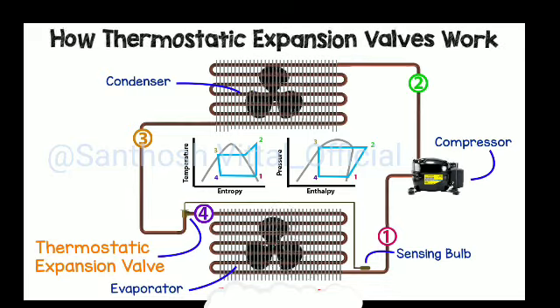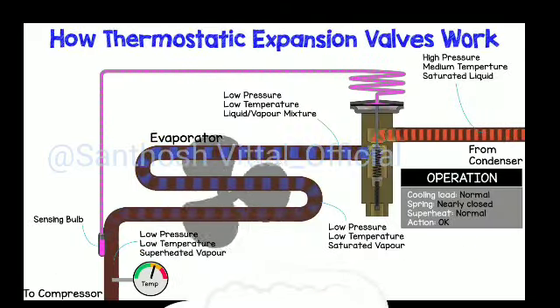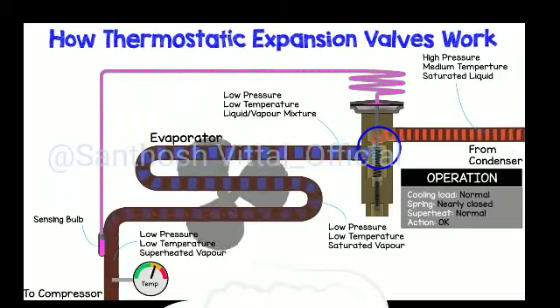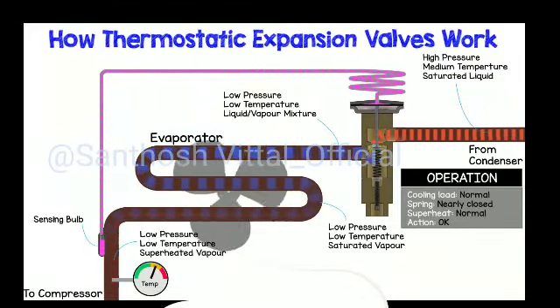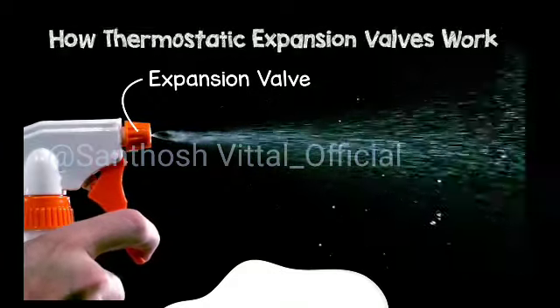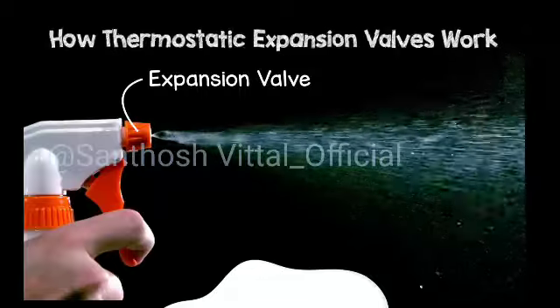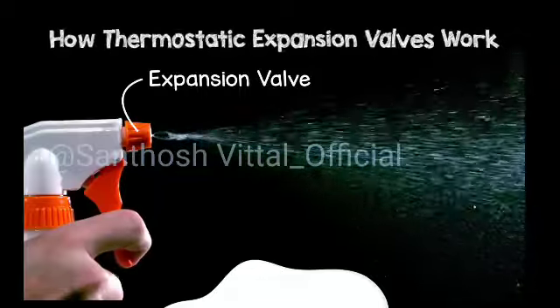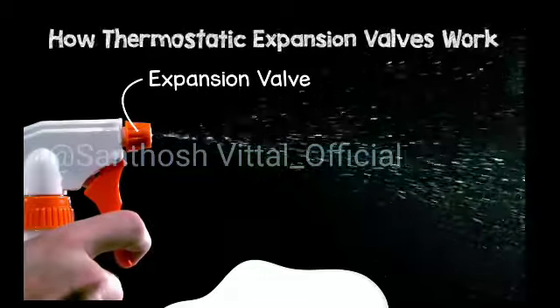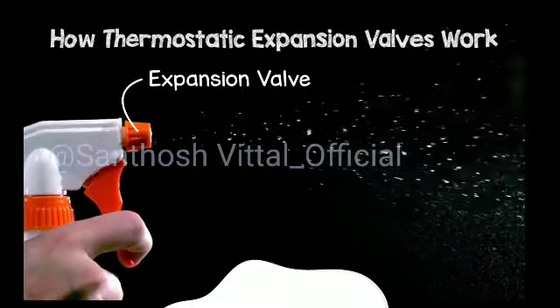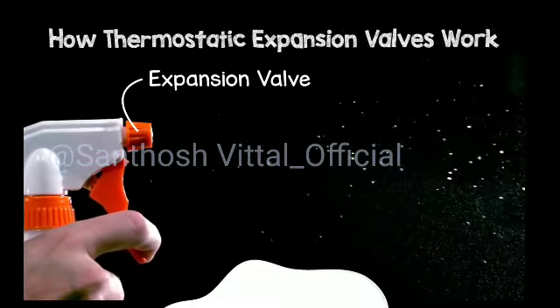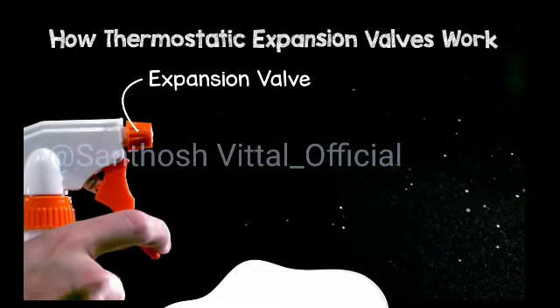Also, just remember that the refrigerant has a much lower boiling point than water. The high pressure liquid is forced through a small orifice, which causes a pressure reduction, and as it passes through here, some of it will vaporize and the rest will remain as liquid. It's similar to a water bottle spray nozzle. As you pull the trigger, the high pressure water is forced through the small orifice into a much lower pressurized atmosphere. This causes the water to become part liquid and part vapor.